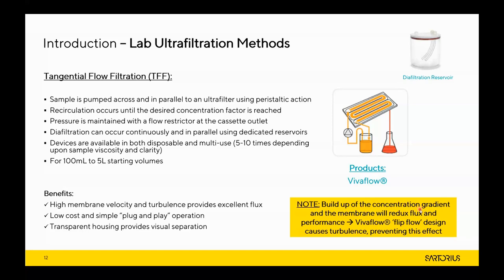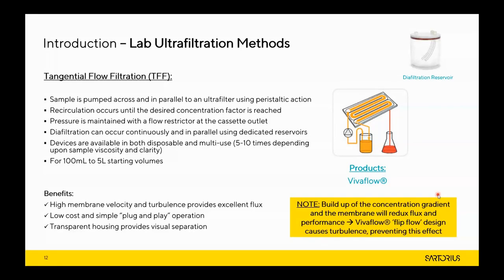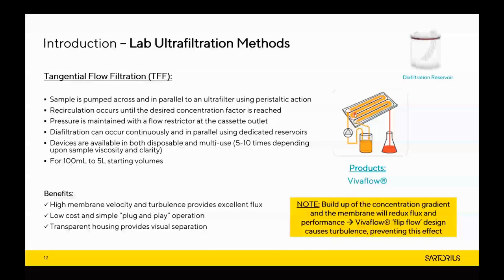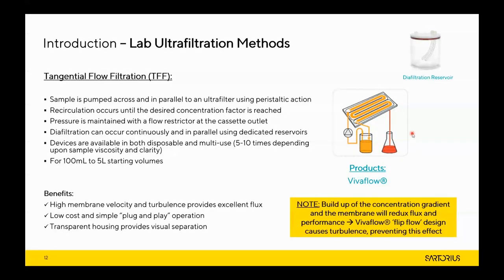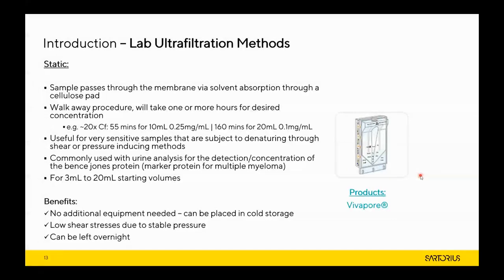With TFF, the concentration gradient at the membrane boundary layer increases membrane fouling, which reduces flux. One of the nice things about the VivaFlow design is the unique flip-flow style: each flip and flow causes turbulence that helps prevent that concentration gradient effect, causes agitation, and reduces membrane boundary layer buildup — making the device easier to use and more forgiving.